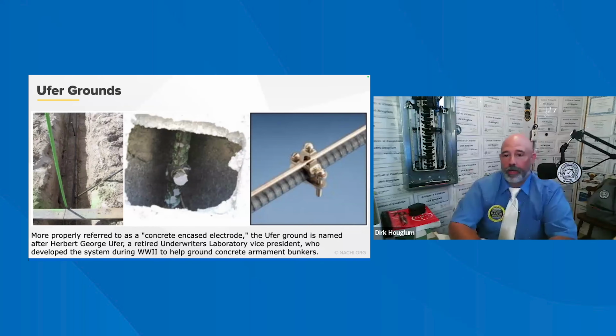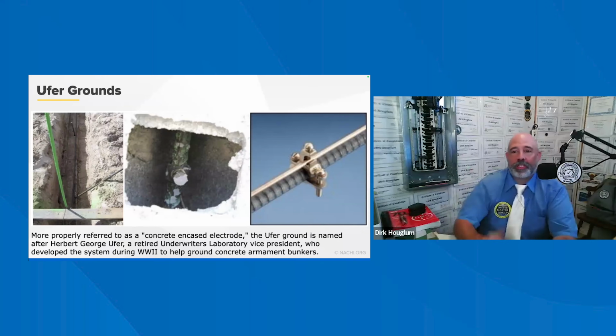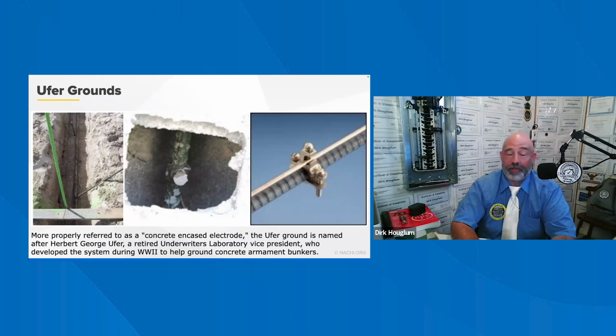Keep moving on. The inspection image here shows both the rebar in place prior to the concrete pour and the above-ground accessibility connection for the grounding system. The rebar is painted green, so it is present and can be verified by the local building inspector having authority.